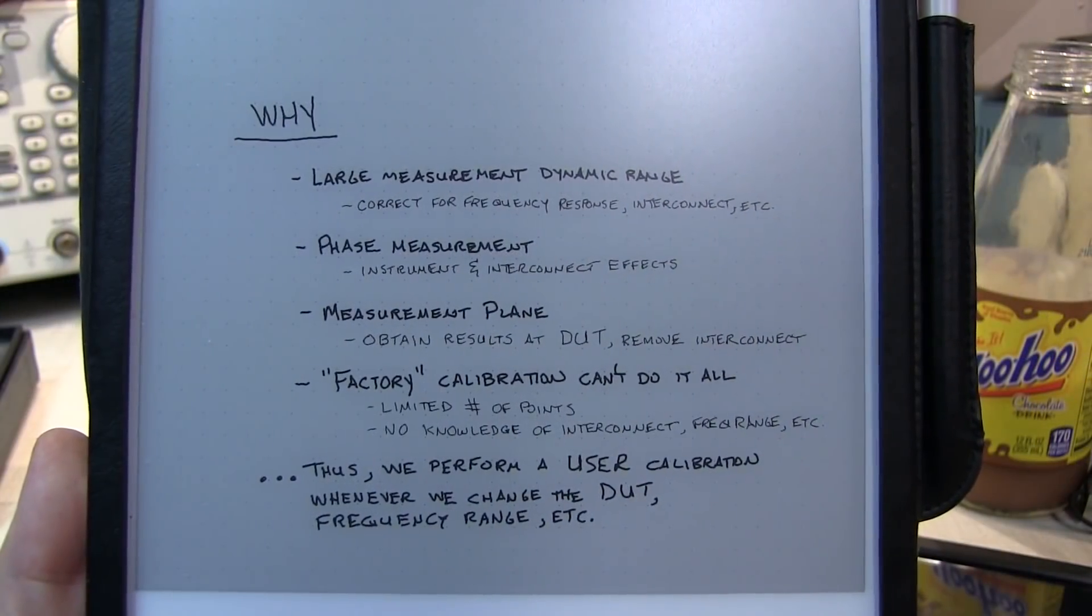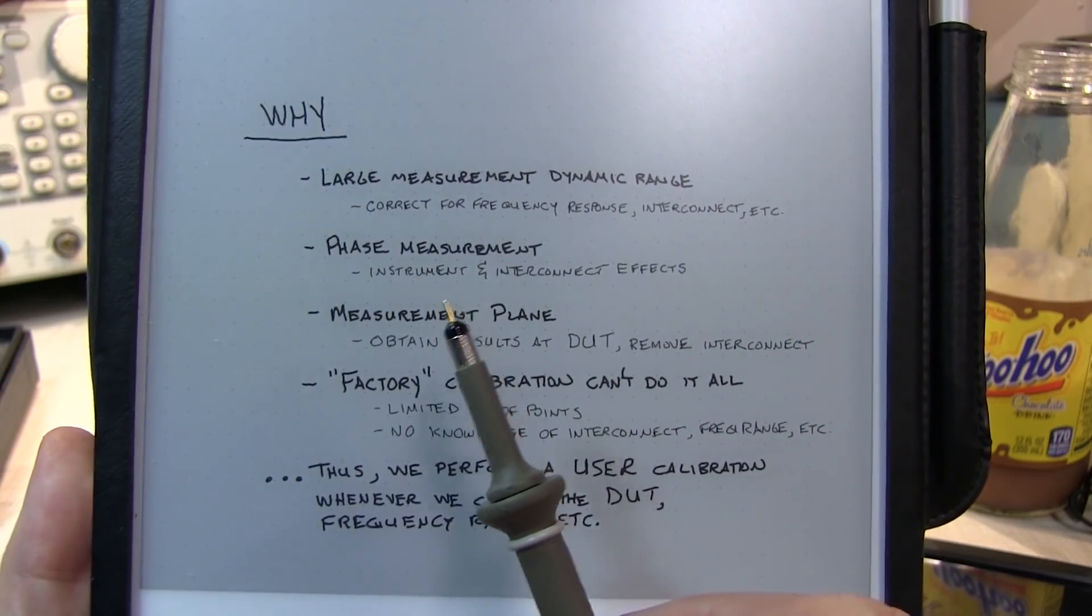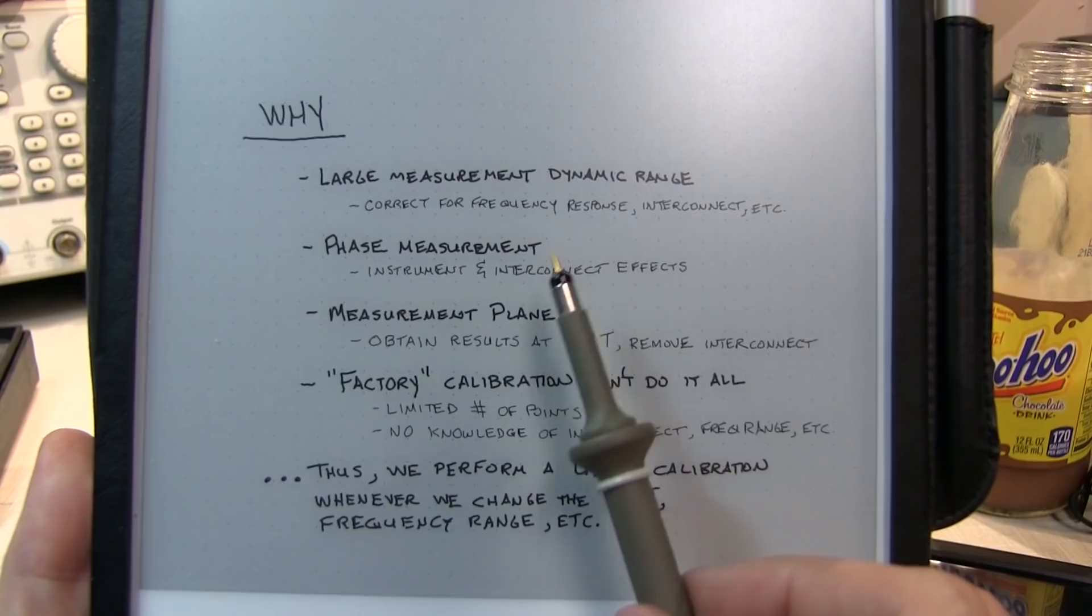Here are the major reasons why we need to calibrate a VNA. Number one is a VNA can give us a very large measurement dynamic range, 60, 80, 100 dB or more. So any minor variations in frequency response of the circuits inside the VNA and the interconnects can all affect the ability to achieve that dynamic range, so we need to correct for those things.